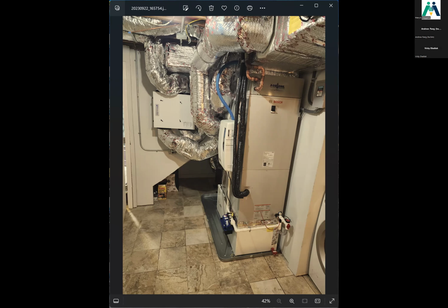The second installation option we have is high velocity heat pump systems. These use a small duct to move air at roughly three times the speed of a regular ducted system. A regular ducted system moves air at about 500 to 700 feet per minute, while the high velocity system moves air at 2,500 to 3,500 feet per minute, so there's a multiple-time difference in airspeed.